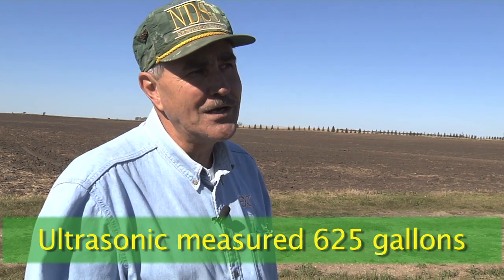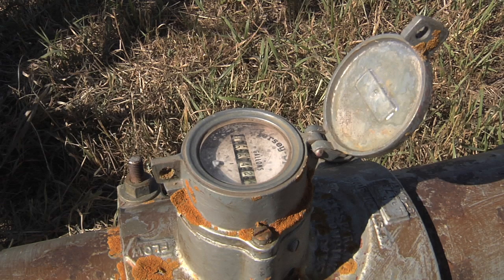So this meter is reading low, which is not unusual. It probably indicates the bearings are getting worn and it's just not turning as smoothly as when it was new. So this would not be a reliable guide for estimating the flow rate from this pump.